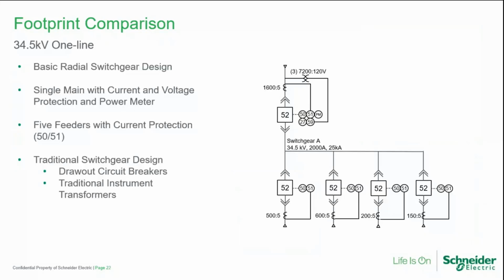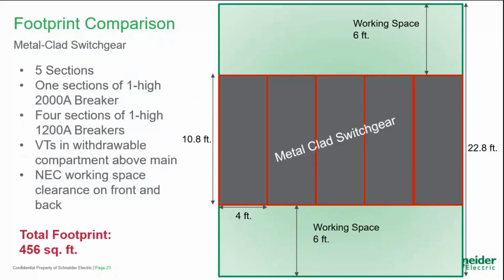Let me look at a 38 kV example. This is 34.5, very common voltage. At 38 kV class. Again, a radial switchgear design, main and 4 breakers, VTs associated with that main. Basic relay protection. If I look at this in 38 kV design, now I'm looking at quite a bit larger size of metal clad switchgear to bump up to 38 kV. 5 sections, 1 2000 amp breaker main, 4 1200 amp breaker feeders, VTs withdrawable above the main, NEC working clearances front and rear, looking at a total of about 456 square feet of space, quite a bit of room.